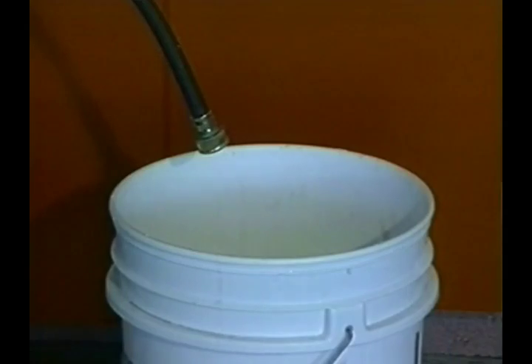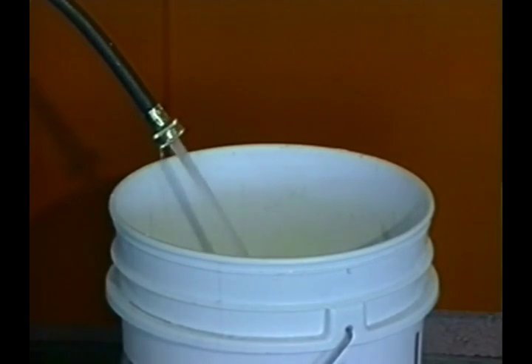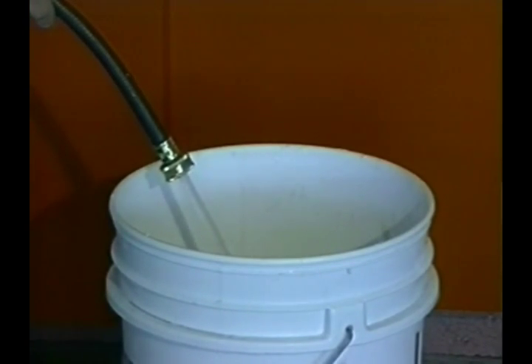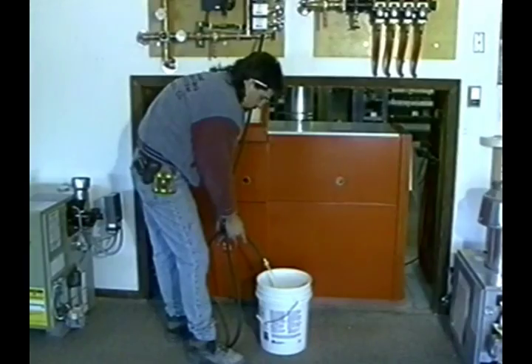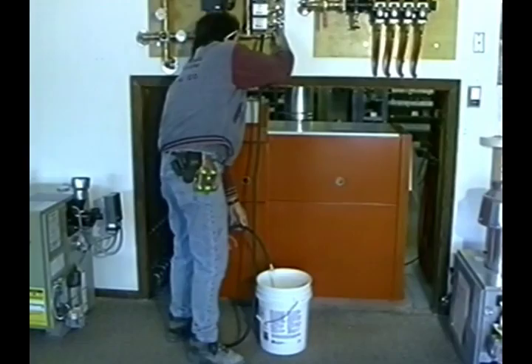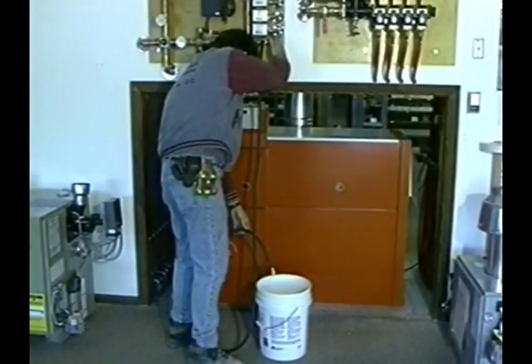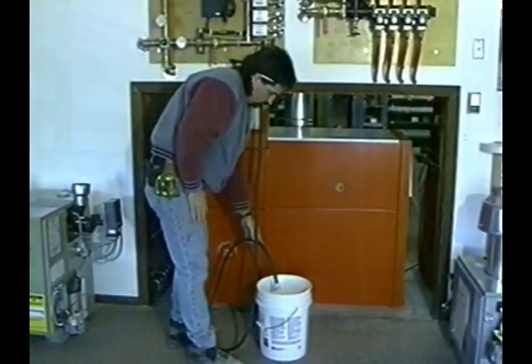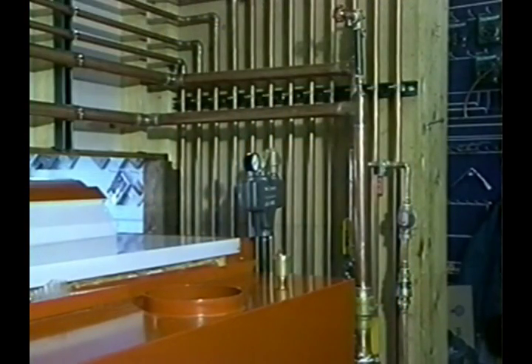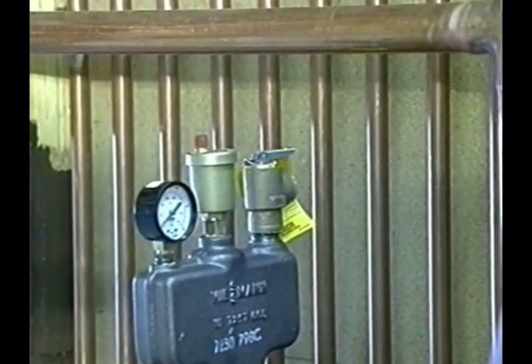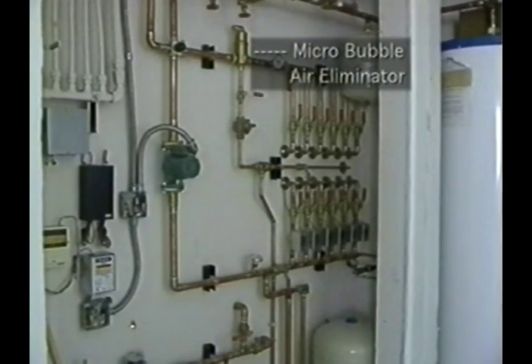The most common complaints about hydronic heating systems are usually related to air in the system. It's vital to remove all air from the system to assure proper operation. Air trapped in tubing or manifolds can prevent proper circulation through in-floor tubes. Problems such as accelerated corrosion of equipment, loss of heat output, reduced circulation, and reduced heat transfer by the distribution system are just a few concerns with trapped air. An air eliminator installed in the system will remove any excess air in the closed system. Microbubble air eliminators are the most efficient available.